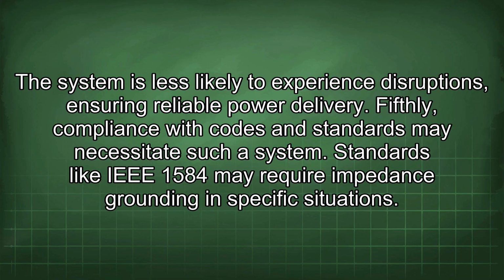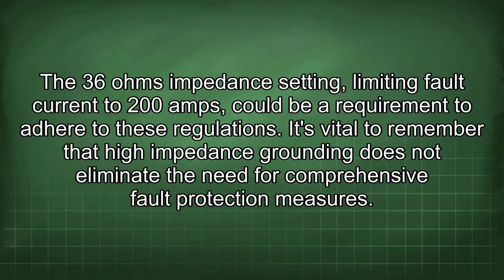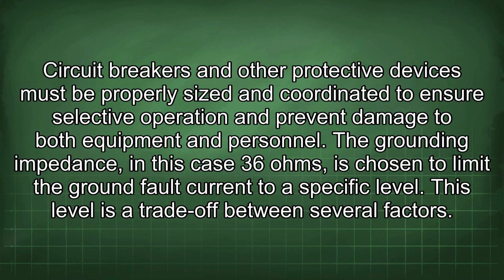Fifthly, compliance with codes and standards may necessitate such a system. Standards like IEEE 1584 may require impedance grounding in specific situations. The 36 ohms impedance setting, limiting fault current to 200 amps, could be a requirement to adhere to these regulations. It's vital to remember that high impedance grounding does not eliminate the need for comprehensive fault protection measures. Circuit breakers and other protective devices must be properly sized and coordinated to ensure selective operation and prevent damage to both equipment and personnel.